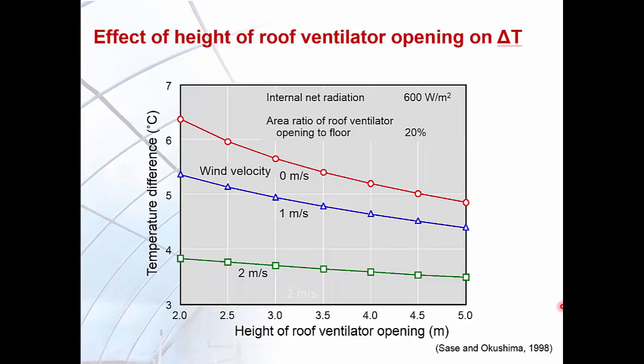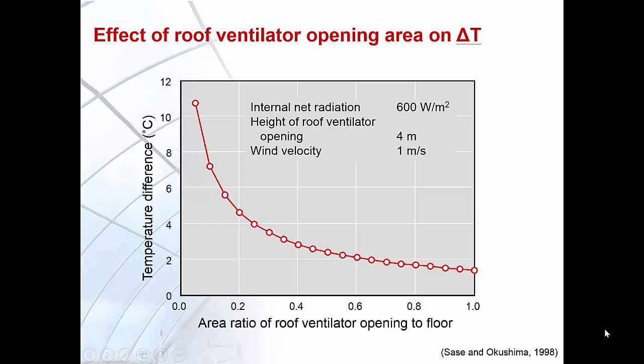This example shows that taller height of the ventilation opening results in greater greenhouse capacity to prevent sudden changes in internal climate, improving spatial uniformity. An additional advantage of taller greenhouses is to promote ventilation caused by the chimney effect and the mixing of cooler incoming air through roof ventilators. The height increase is especially effective when external wind velocity is low or under stagnant air conditions.